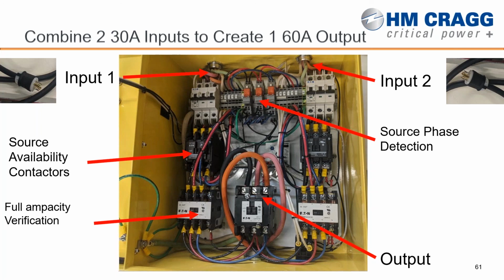The next set of contactors you see is for full ampacity verification. So exactly what I said, we're not going to be drawing 60 amps off of a single 30 amp source. It will kill the main output contactor before that happens. This was a very custom opportunity, we had a lot of design work into this, and we're pretty proud of the product we developed for this application.